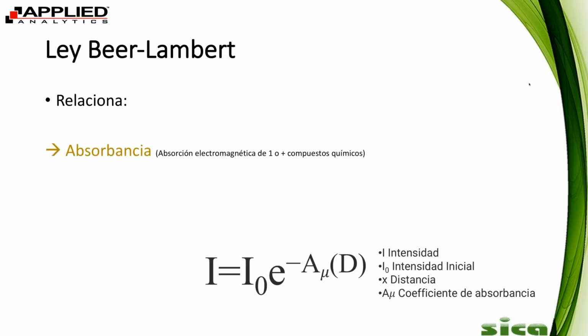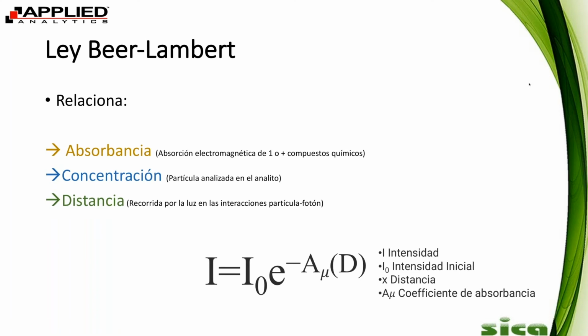So like I mentioned before, our detector, our spectrometer, is based off of the mathematical law of Beer-Lambert's law, which basically says that absorbance and concentration are correlated. Of course, there are different variables in correlating these two things. For example, there's light intensity, there's distance of path length, but here you can see where we measure the light intensity exiting the sample, which would be I. So that's sort of what the detector is actually doing. It's sending a light intensity into a flow cell where it interacts with the sample, and then the light intensity coming out is the first thing basically being calculated.